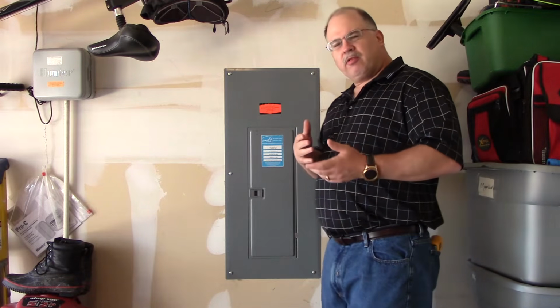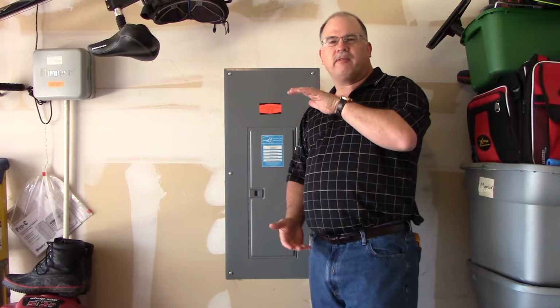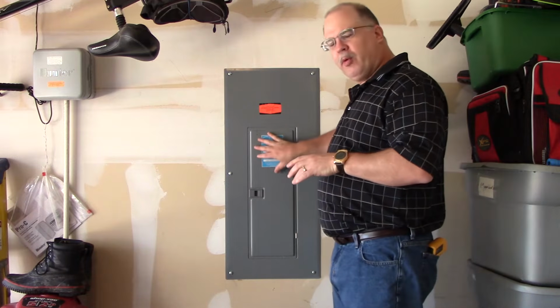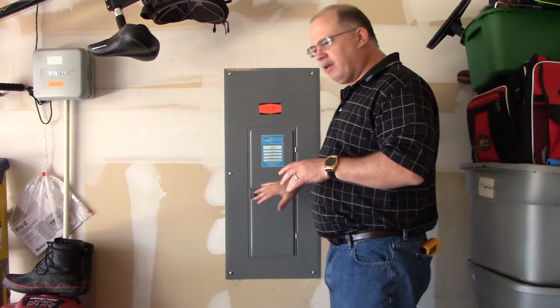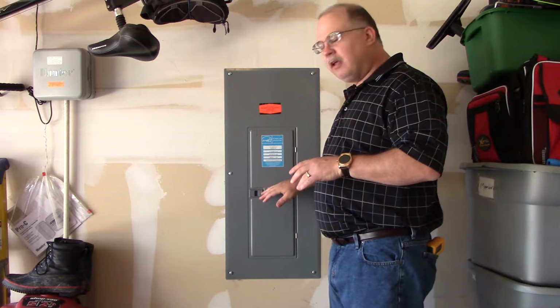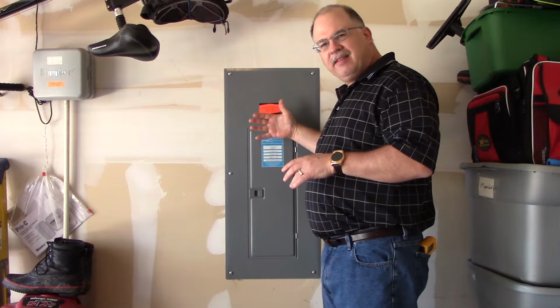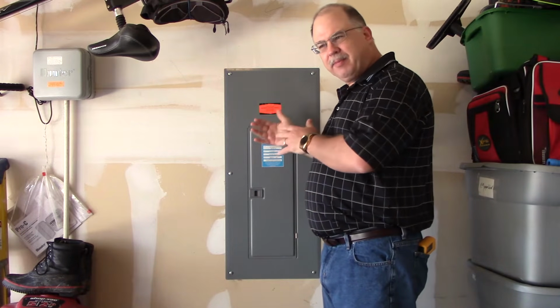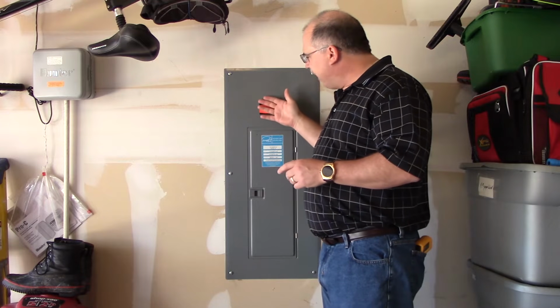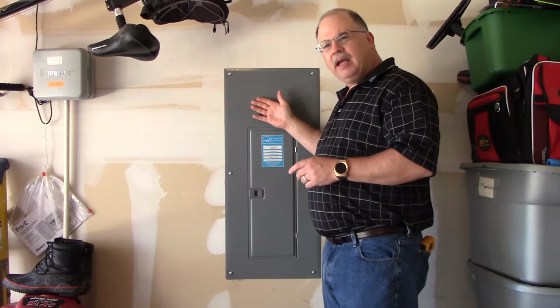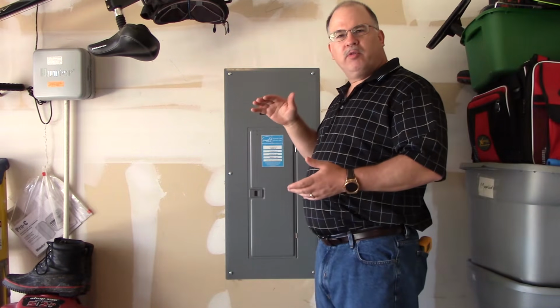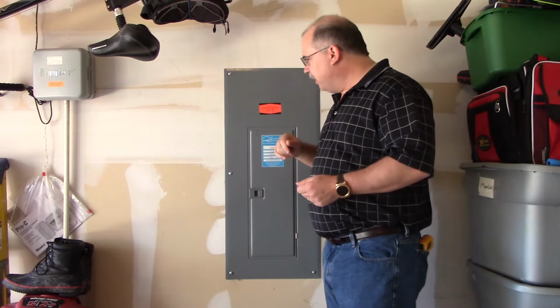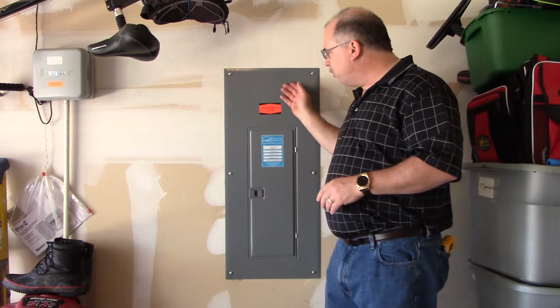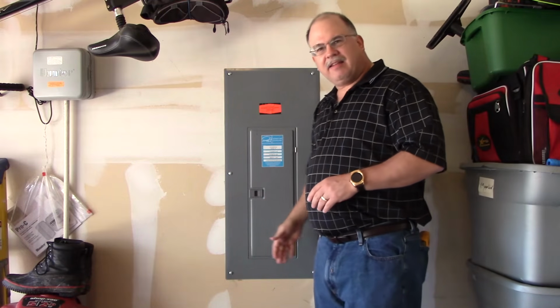Now, there's a method to removing a cover, and we're going to use the cover for what's intended. Not only is it to help hold the breakers in and to help keep the exposure to all live parts, if there's any incident that takes place, it's going to help protect it from getting out. But now we're going to actually use this cover as a blast shield as we remove it during the inspection process. Now, the one thing we're going to do before we do that is we want to make sure before we do it that it's not energized.